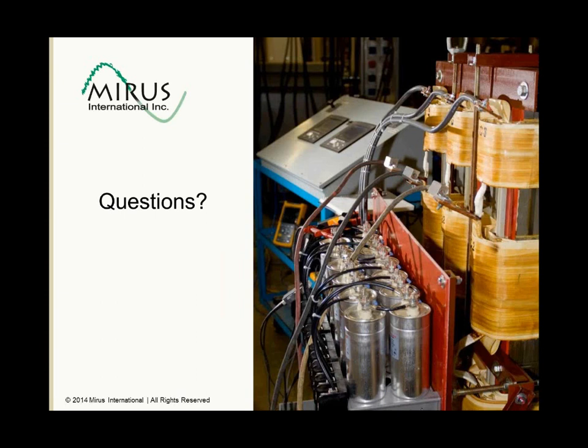So it is often required by those competitive filters that contactors be used to switch out the capacitors at light loads. Our filters are designed intentionally to have low capacitive reactance. We guarantee less than 15% capacitive reactance. At levels that low, it's not going to introduce problems on generators. It's not going to introduce voltage boost issues on power systems. So with our filters, there's no requirement for switching out the capacitors under light loads. But I would say that with other passive filters, it is a requirement.